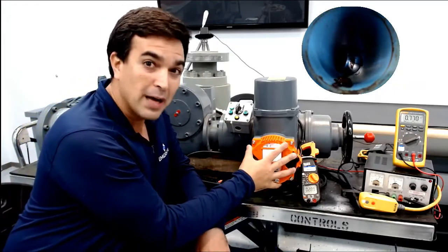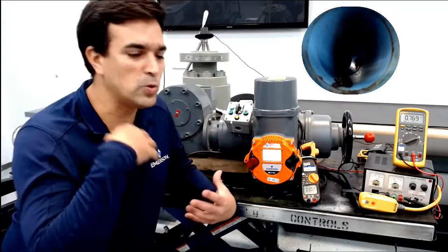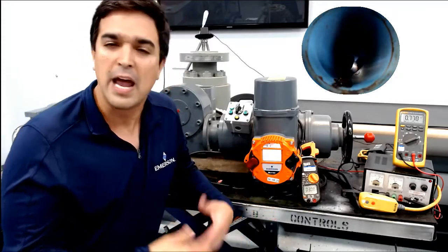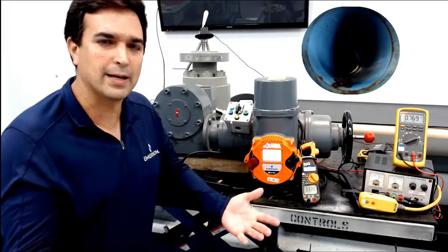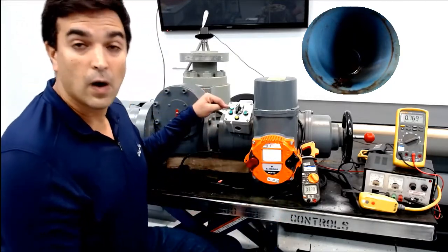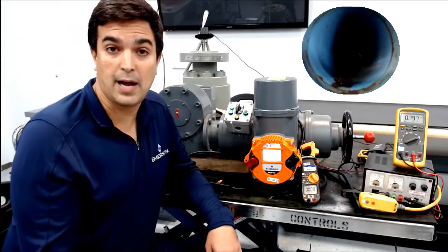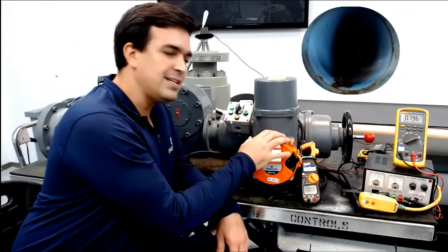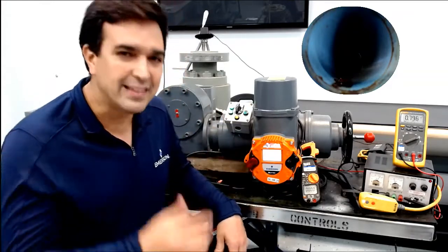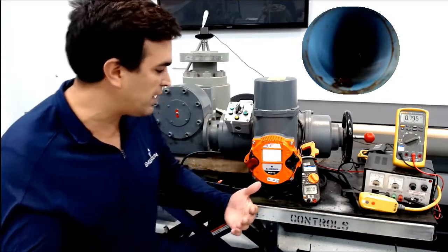The first one you can do automatically on this device. You can set up this unit to trigger the partial stroke every year, every month, at 1, 2, 3 p.m., at the time that you want, and you are going to have the feedback on your system, or you can come back here and see if the last partial stroke was okay. And if not, you can do something before the system demands that valve. That is the most important thing, and that is the way that you increase reliability.